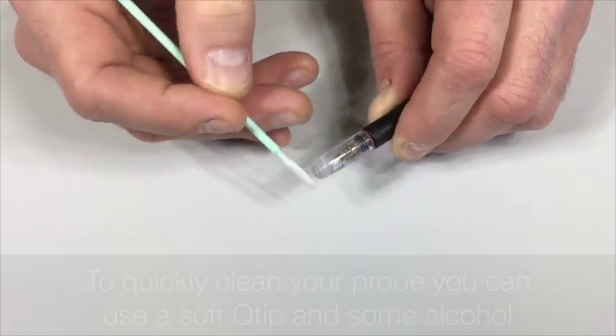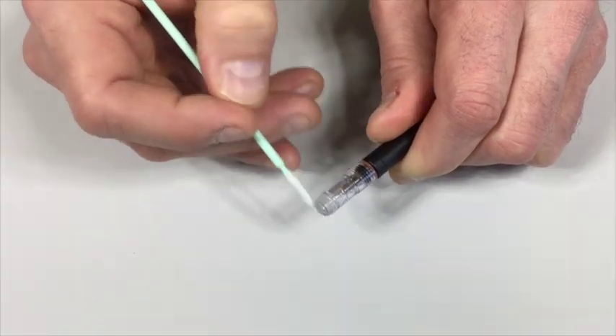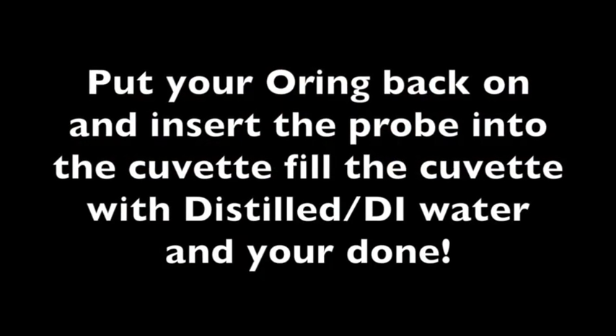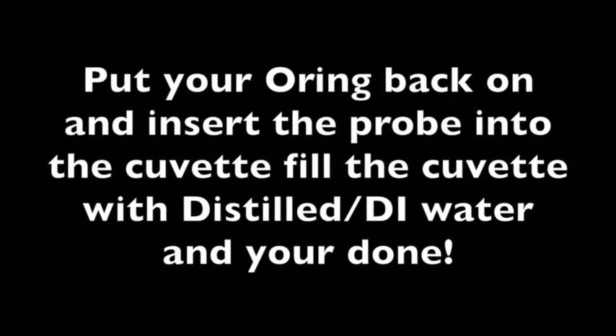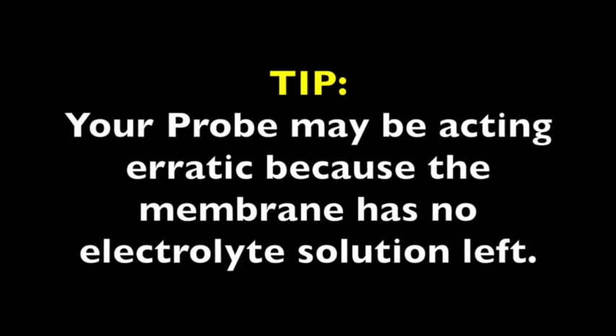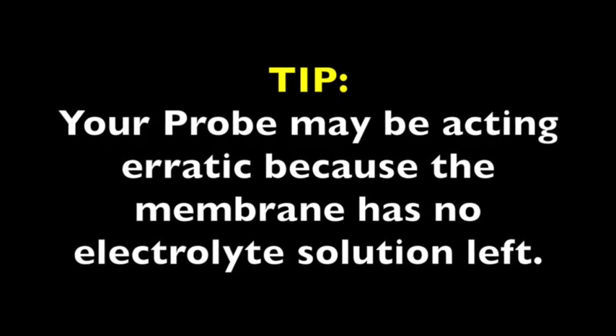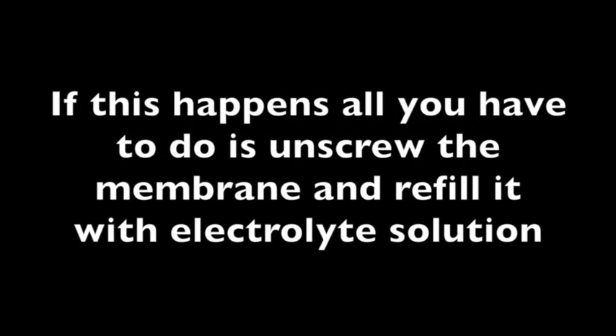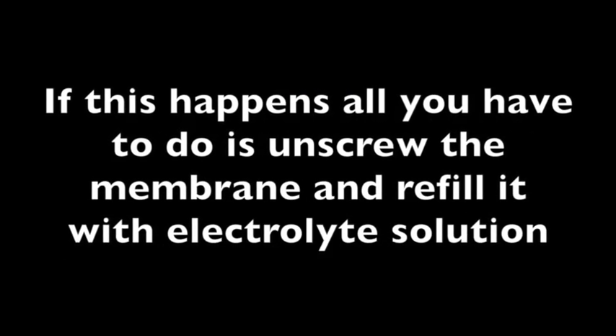To quickly clean your probe, you can use a soft Q-tip and some alcohol. Gently rub the tip and turn the probe as you clean. Put your O-ring back on, insert the probe into the cuvette, fill the cuvette with distilled or DI water, and you're done. Your probe may be acting erratic because the membrane has no electrolyte solution left in it. If this happens, all you have to do is unscrew the membrane and refill it with electrolyte solution.